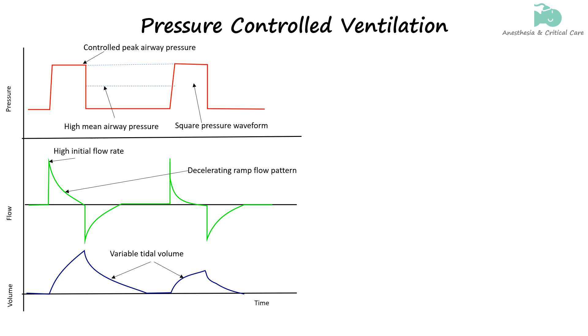In a pressure-controlled mode of ventilation, the inspiratory pressure is the control variable and is maintained during the inspiratory phase. As a result, the pressure waveform is square, which increases the mean airway pressure. During the early inspiratory phase, the ventilator provides a high inspiratory flow rate to rapidly achieve the pressure limit. In order to maintain this pressure, the flow rate needs to decrease over the course of inspiration, generally taking the shape of a down-sloping ramp. The tidal volume fluctuates depending upon the lung compliance.